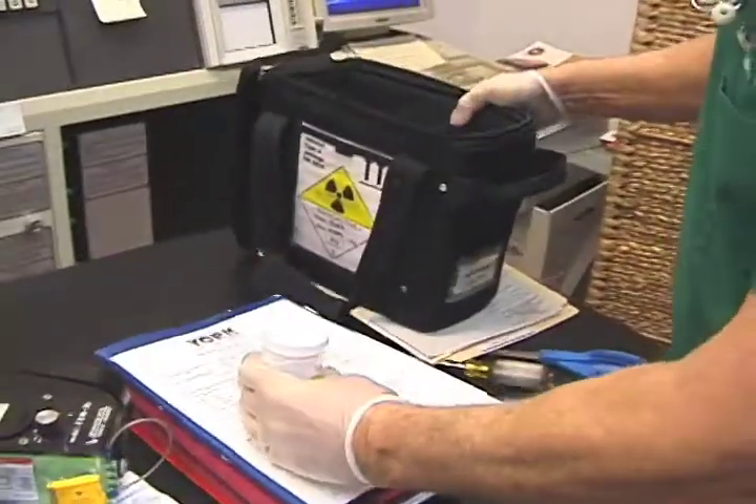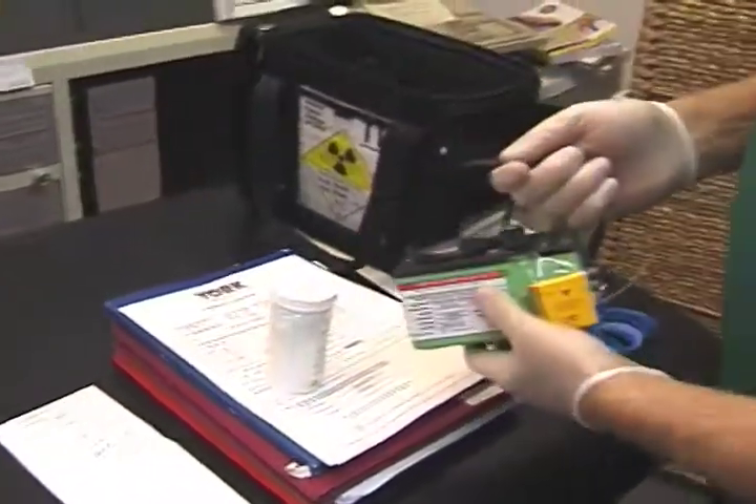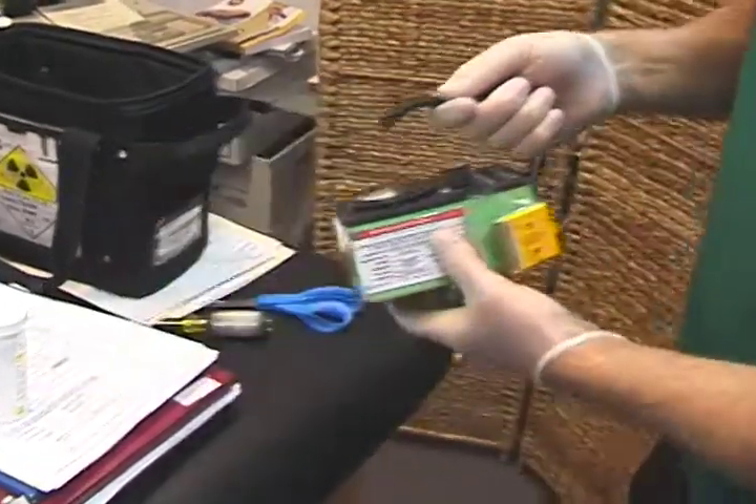The first thing we have to do is make sure there's no leakage of the radiation from the container, so we take it out and use a Geiger counter right at the edge and also in the back to make sure there's no leakage — and there's no leakage.